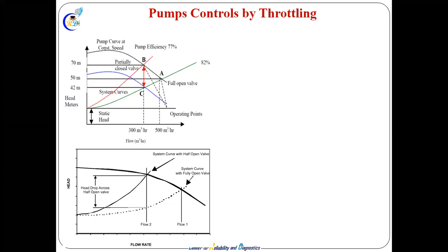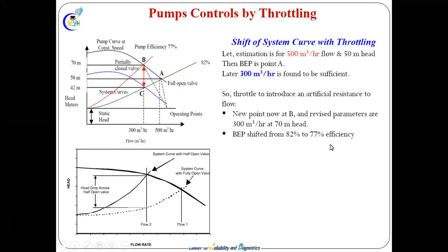Instead of spending more energy by throttling, put the RPM lower, because this is the constant speed pump, and with the VFD you are talking about, if we run the VFD at a lower speed, we get this blue curve, and the blue curve satisfies my system curve which is available at the site, right? So our intention of going from 500 to 300 cubic meters per hour is satisfied with less energy. I think everything is clear now. So speed control is always better than throttling. Okay, because the system curve is the bottom one, it has to flow like this. In an example, if you shift, the new point comes from 82 to 77%.